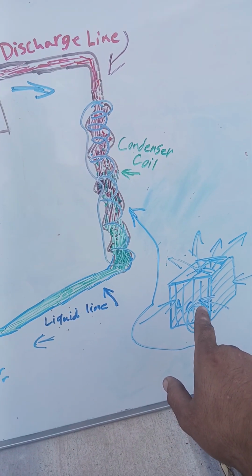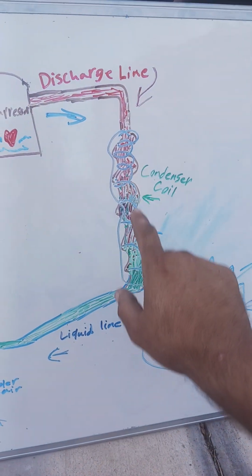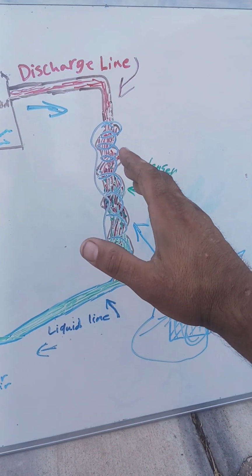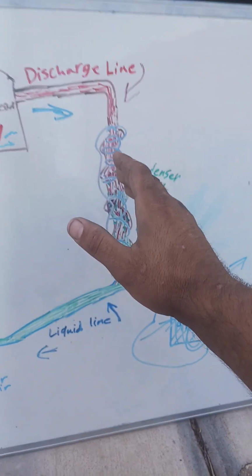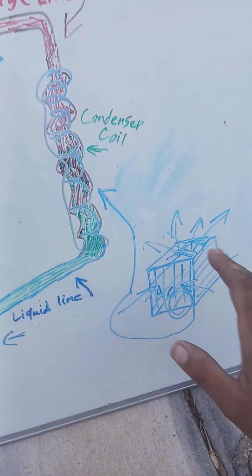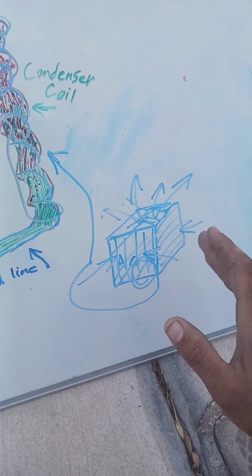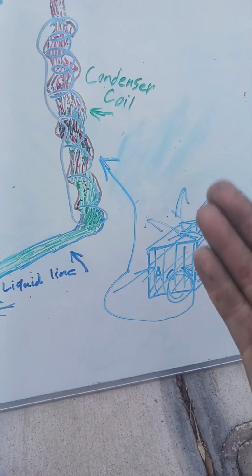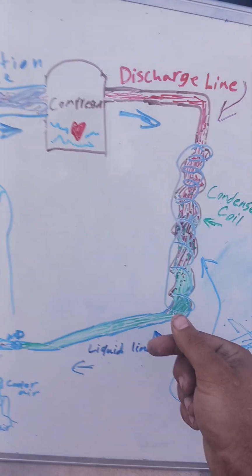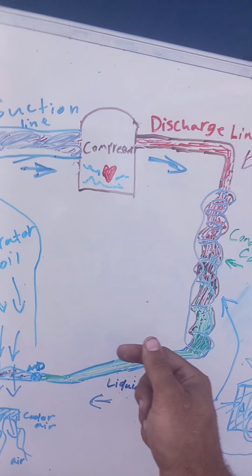This is your condenser. This is your coil. The black box I showed you outside, this is what it is in the drawing, obviously, but I drew it for real what it looks like. But this is what's going on. If you can look closely, disregard the blue, you see hot gas as the fan pulls air through the side and out the top. It's pulling cooler air to remove the heat from the gas inside the line, so that way it starts to condense into a liquid.